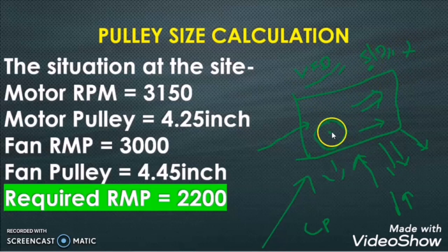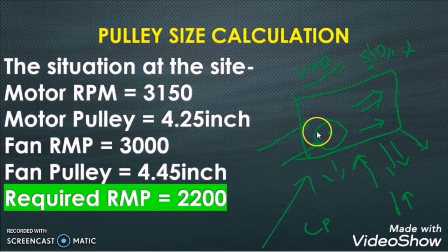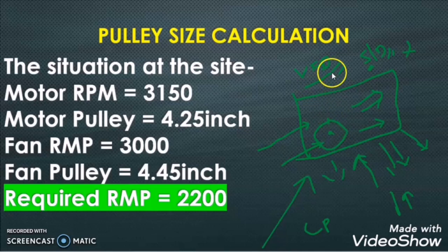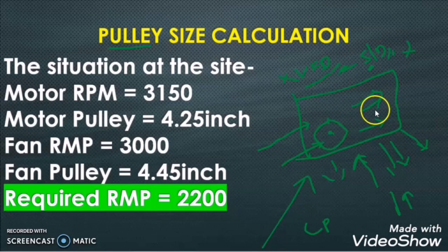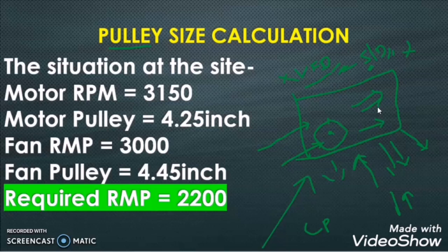We cannot run the motor all the time in star configuration and we don't have a VFD. The third solution would be to replace the motor with a lower RPM rating, but that is not practical due to the huge cost. Buying a VFD was also ruled out due to cost impact. The last solution is the pulley — if we change the pulley at the motor or fan blade side, we can reduce the RPM of the fan, reducing air flow velocity so the air will no longer carry water droplets.